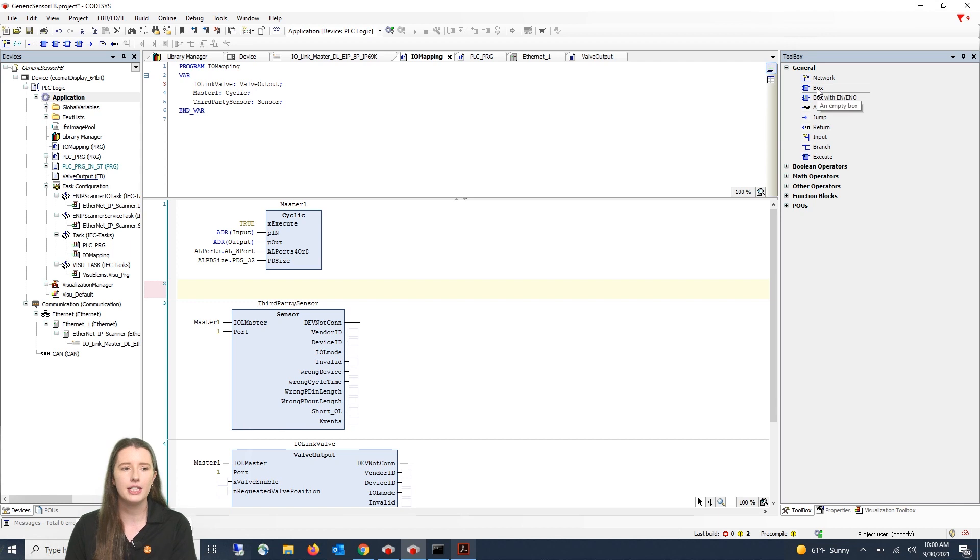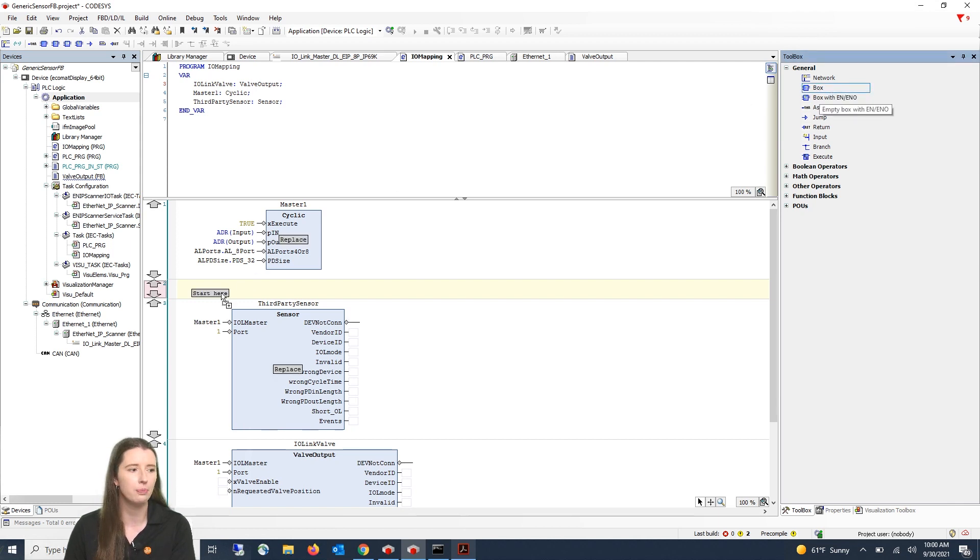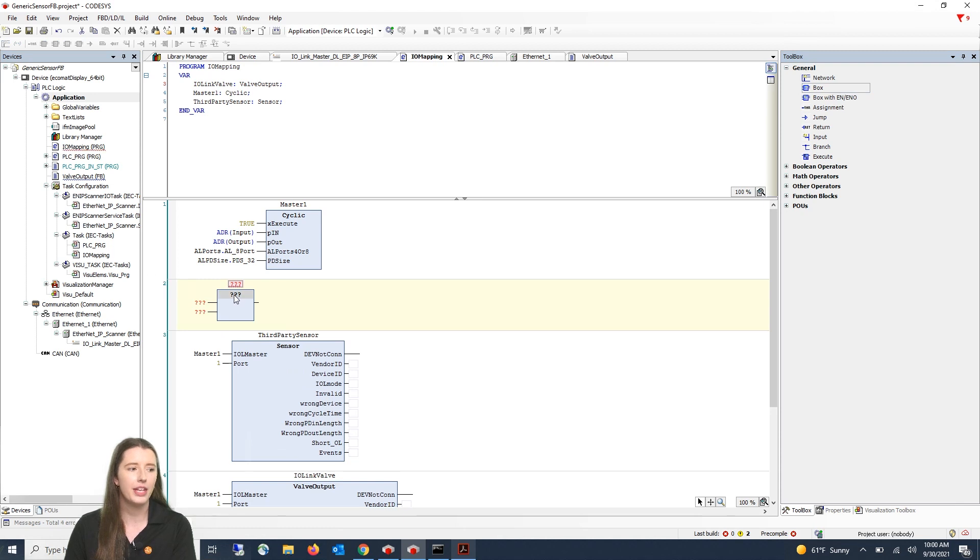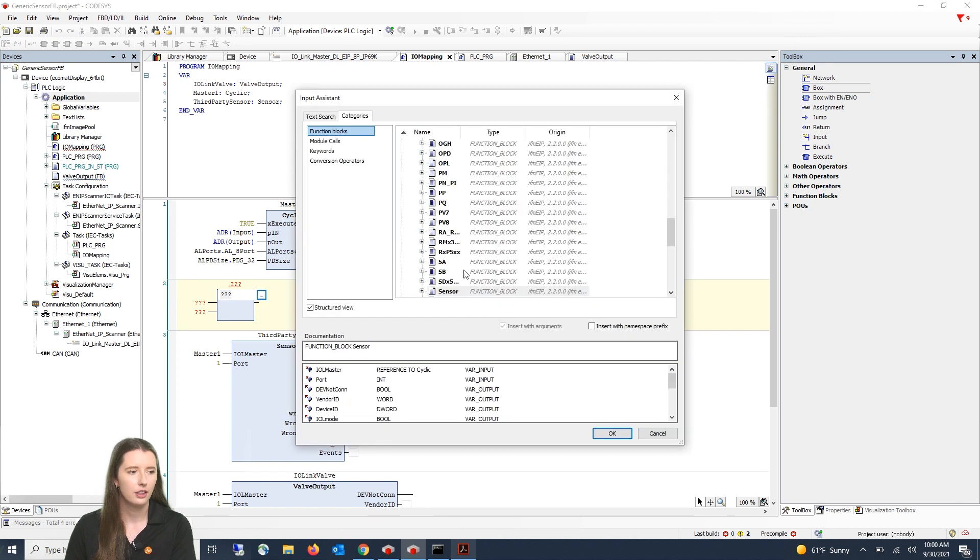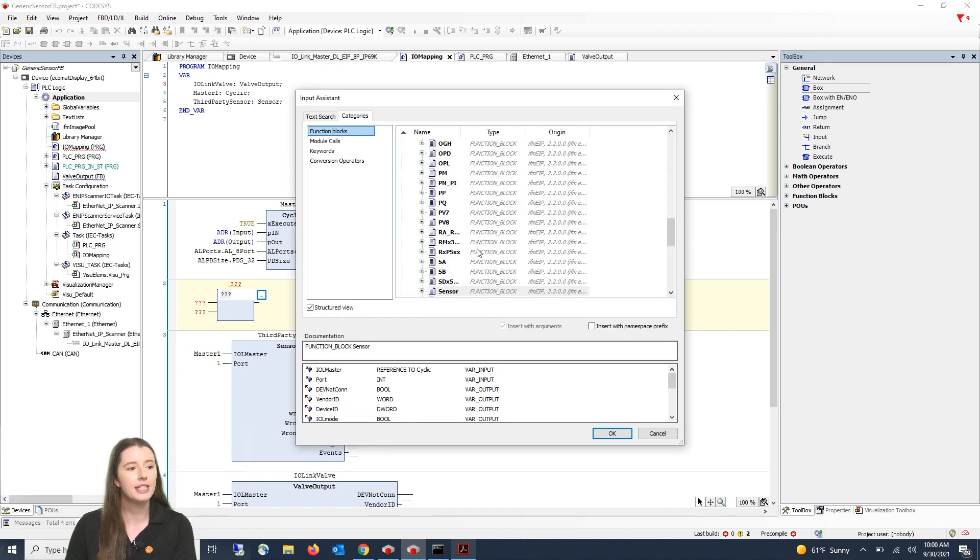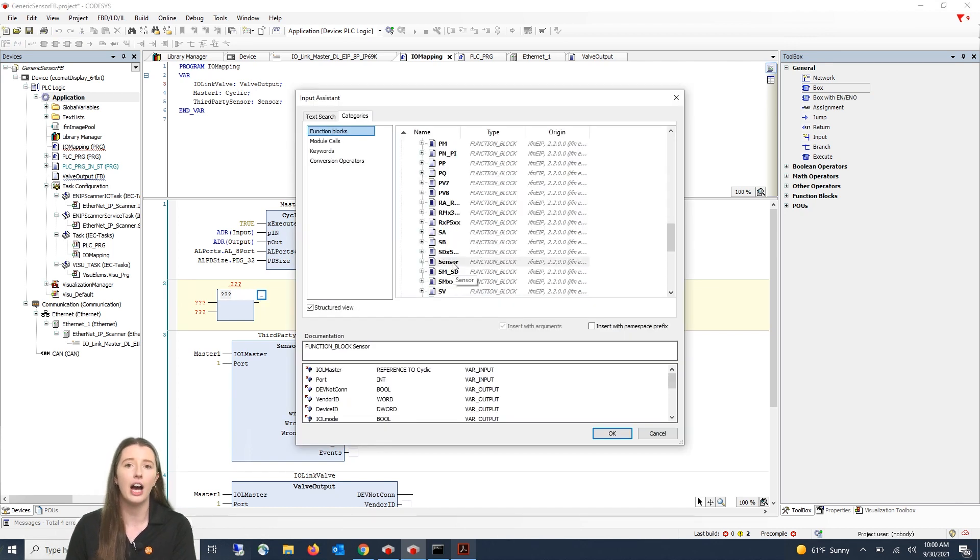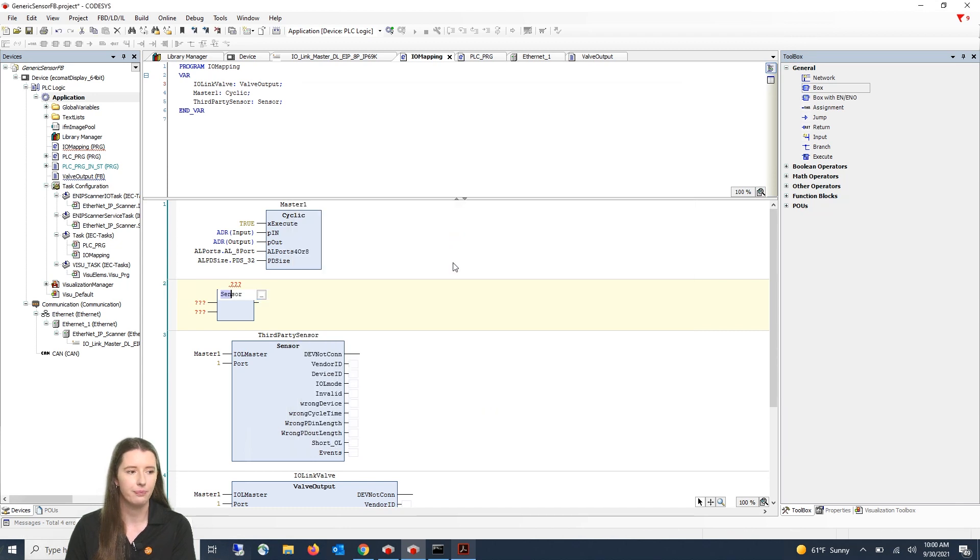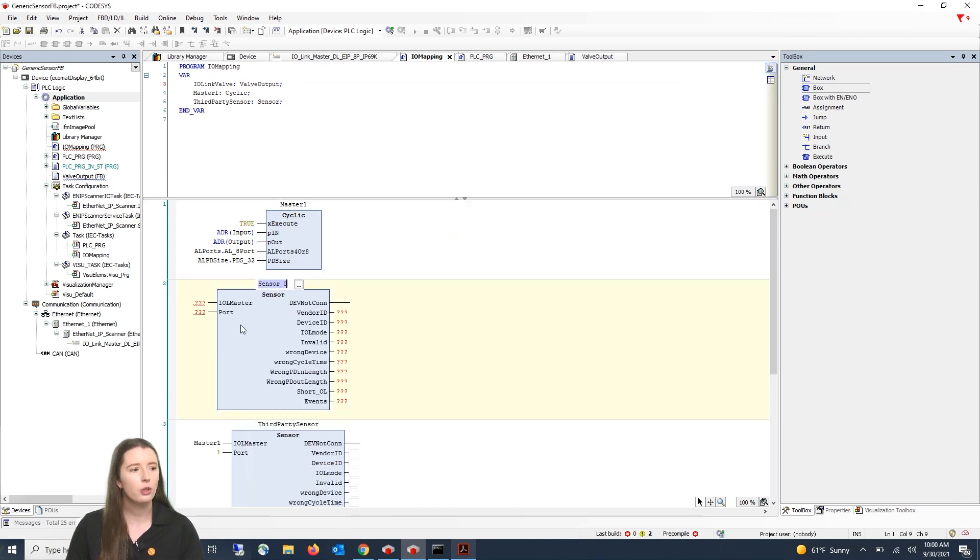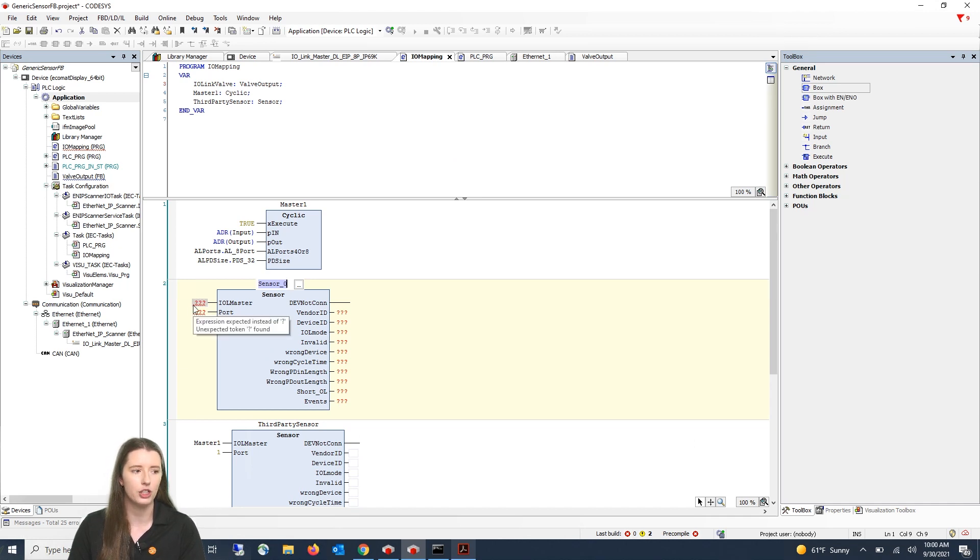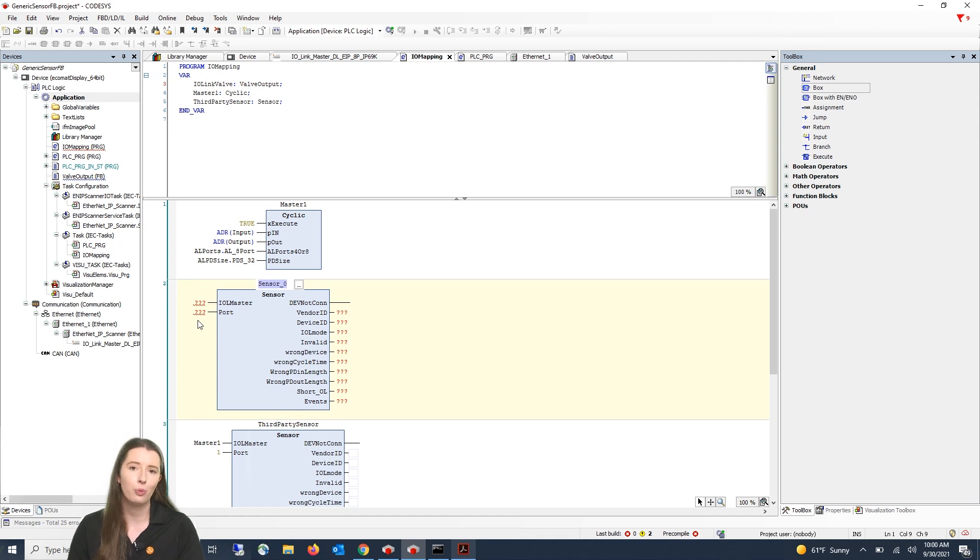On the right hand side under your toolbox you will drag in a general box function block and then within the box if you click on the question marks and on the three dots to the right you can then select the sensor function block out of your IFM function block library. Once you press enter you will then point your master cyclic data at the IO-Link master variable as well as enter the port number that your third-party device is connected to.